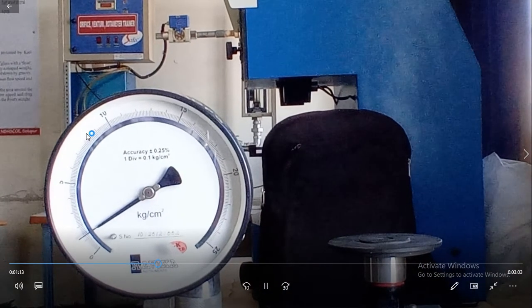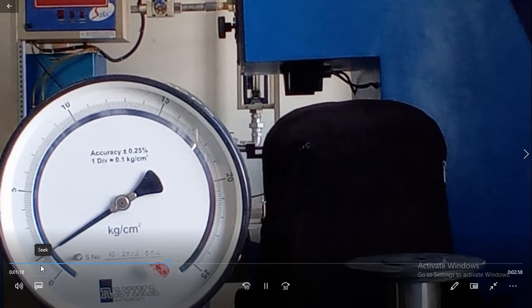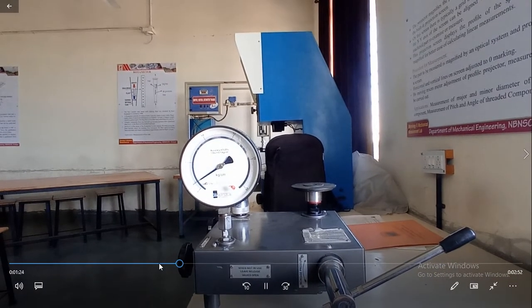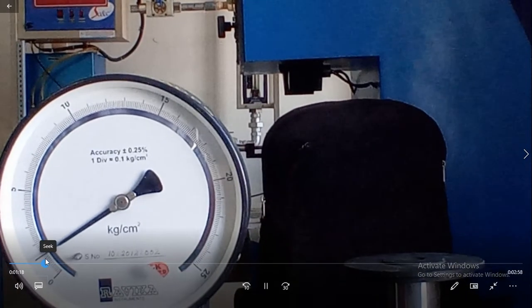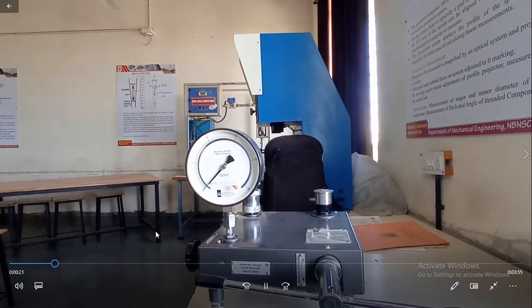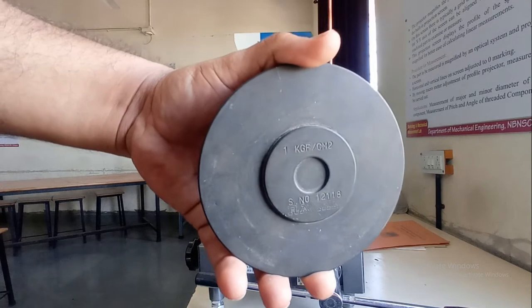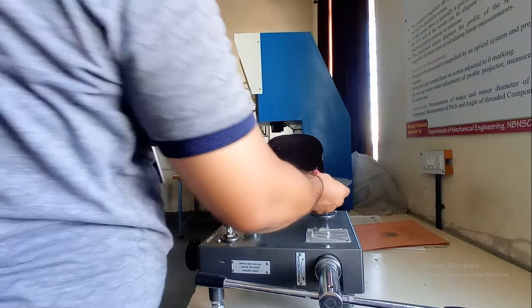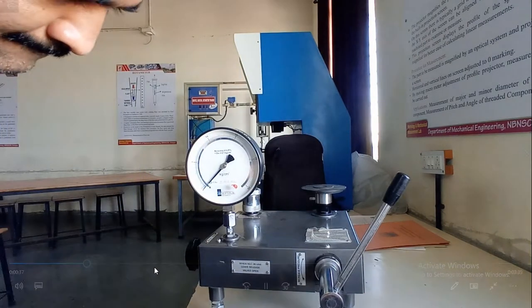The scale reads 5, 10, 15, 20, meaning the first division is 0.1 kg per cm². In this case, the reading observed is 1.2 kg per cm². So in the first reading, we observed that the Bourdon Tube Pressure Gauge is showing 1.2 kg per cm².